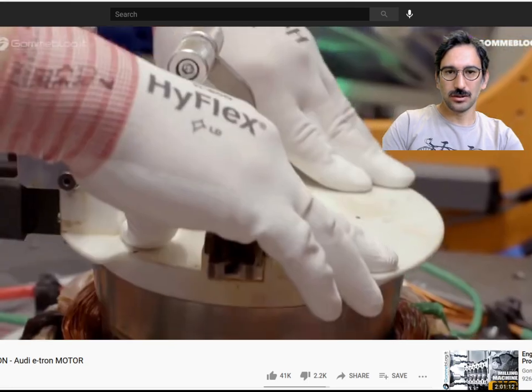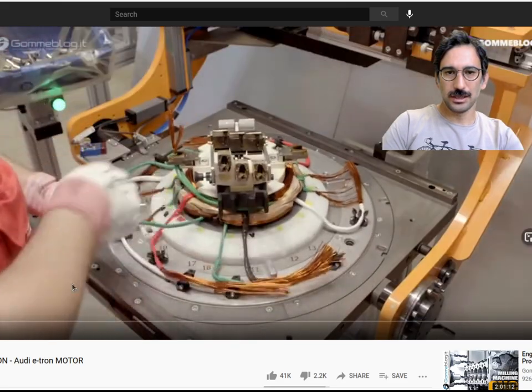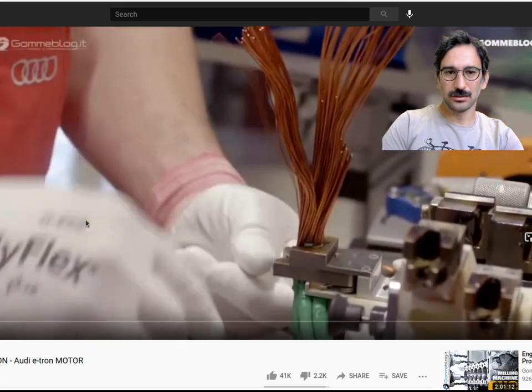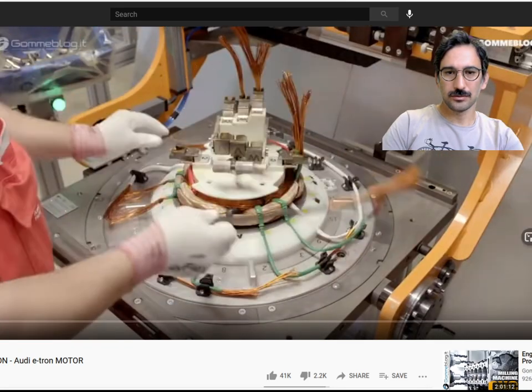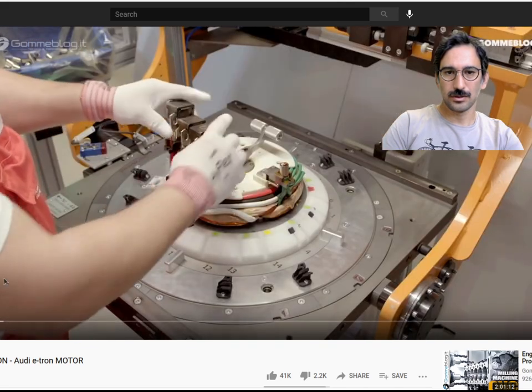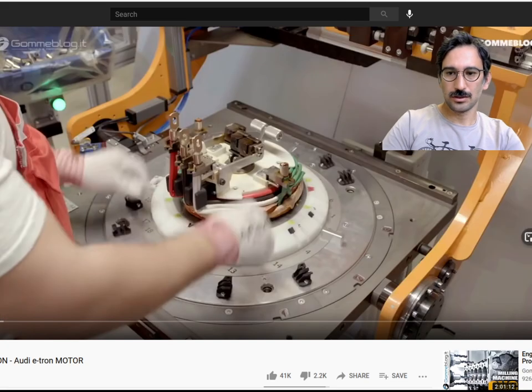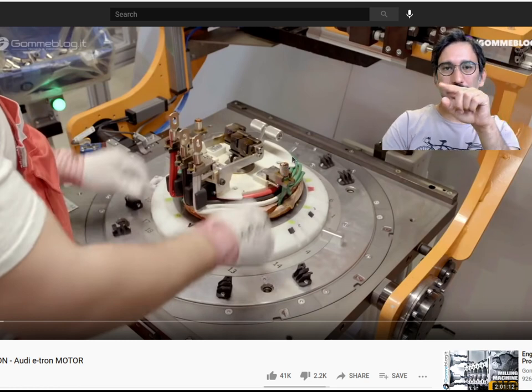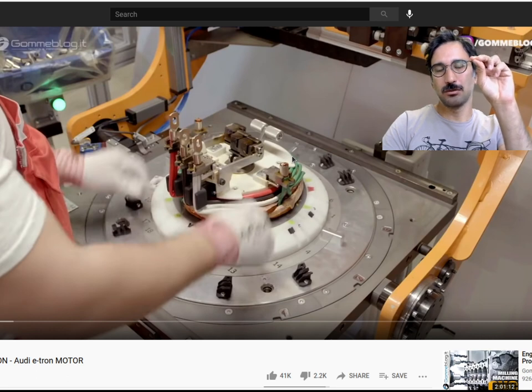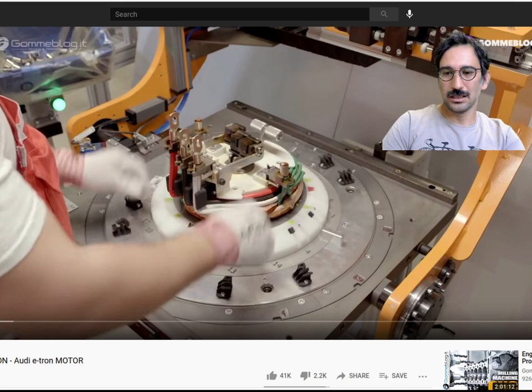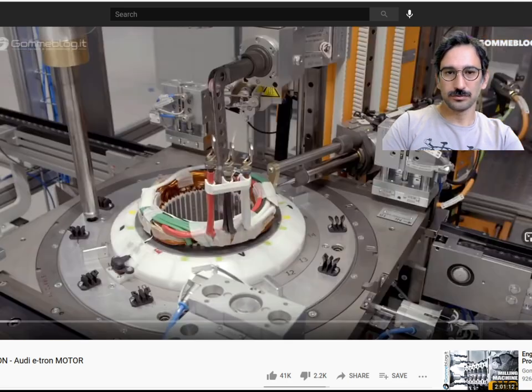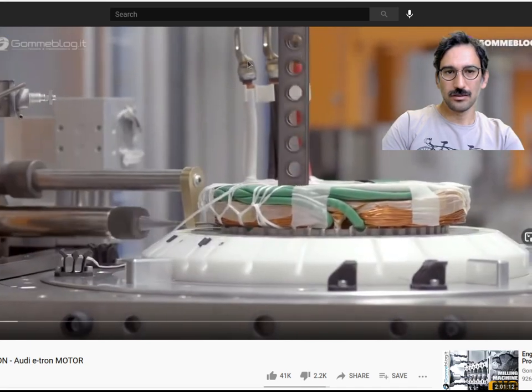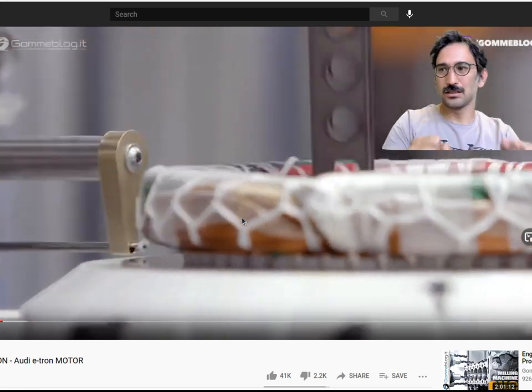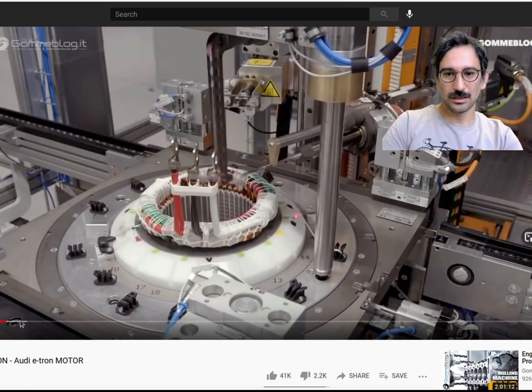So that is, I think, the terminal part. Let's see how many cables are coming out of that one, right? They are connecting all of those. Okay, see, this is the power, let's go a little bit. So these are all the power connectors, right? They have 1, 2, 3 connections, and probably that is the common point. They are connected in a Y arrangement, and the Y point, the common point, is left inside the motor, and you have just three cables coming out of the motor. So it's the three phase connections, and they are winding it for mechanical rigidness for that purpose.